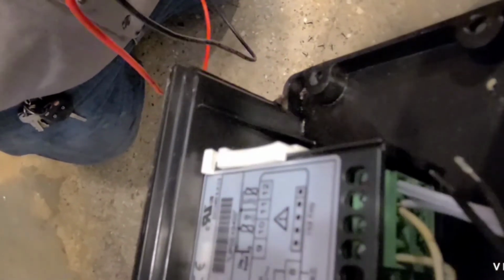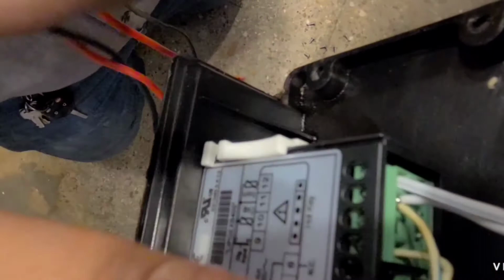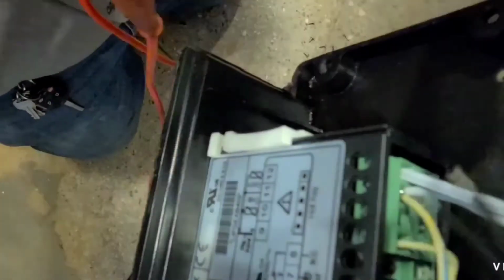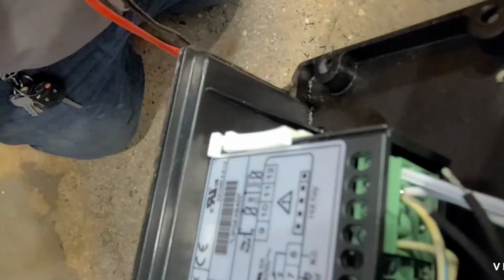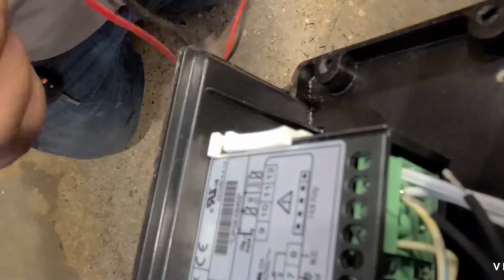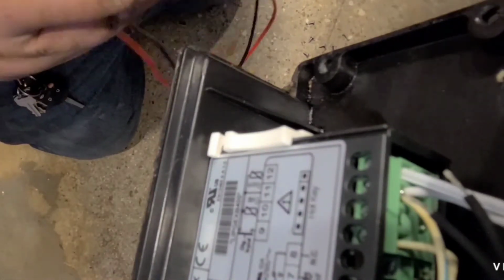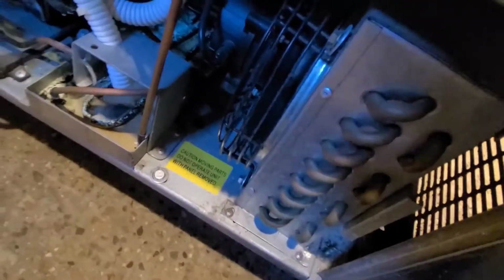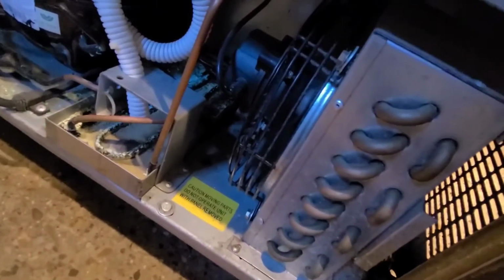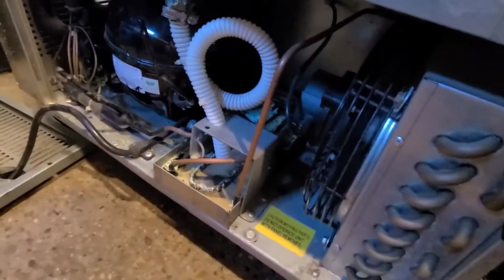Alright, so I'm using ohms of resistance to check the leads. The black one is the evaporator probe sensor. And checking the resistance, I'm getting OL. On the white leads, which is the room box temp, I'm getting resistance, but not on the black leads for the evaporator probe. Not getting nothing. I'm gonna look up that code from the PDF manual.